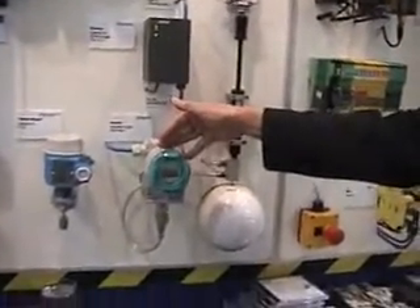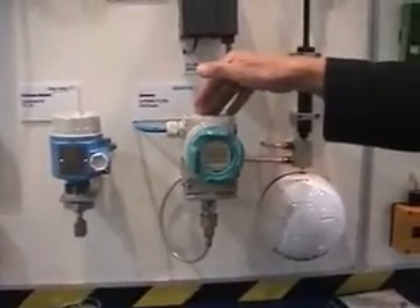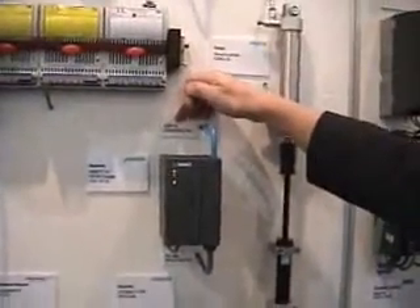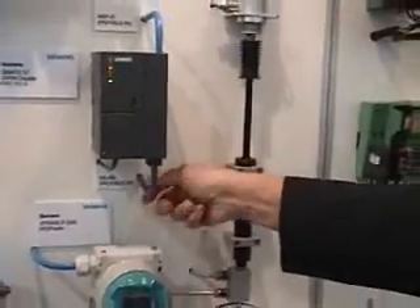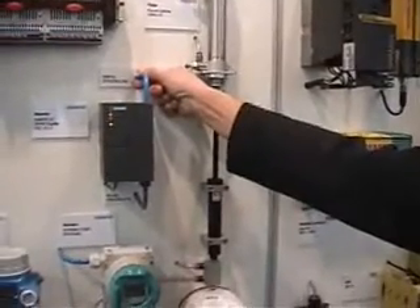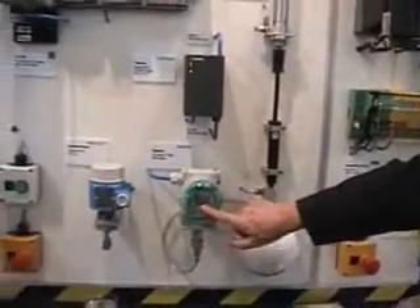Here we have a direct implementation of ProfiSafe in a pressure transmitter from Siemens — the SITRANS P. This device allows you to transfer process data directly via Profibus PA, or MBP-IS technology, with 32 kilobit per second. Therefore, we need a coupler here to come in with Profibus DP and go out with MBP-IS, which is also intrinsically safe. This device can be used for ProfiSafe as well — you just switch on the additional ProfiSafe mechanism, and then you are transferring the pressure measurement value up to the processor.